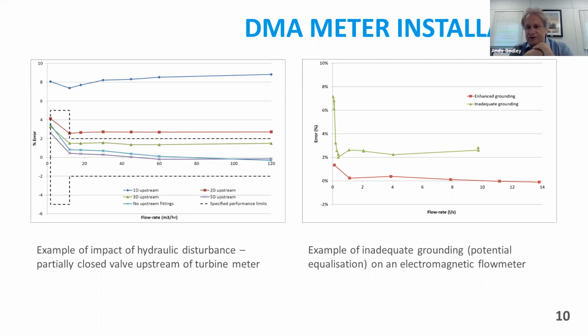So I think that illustrates quite clearly that with an electromagnetic meter, particularly on a district application, a DMA application, you really need to be very careful about the earthing, because obviously there are lots of power cables in the ground. You've got railways and other potential sources that can set up fields, whether it's electrical fields within the earth, or interference on the water that sets up some sort of electrical effect. I don't know. I'm not an electronics expert, but clearly there are effects like that that can happen. So you have to take great care with the earthing, because 2% could be quite a misleading figure when you're looking at a water balance across a particular district.